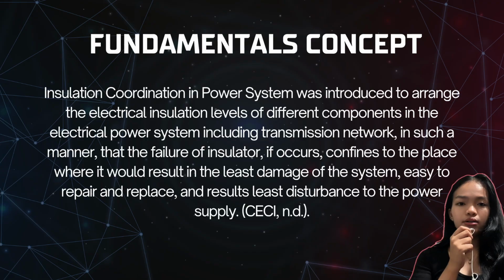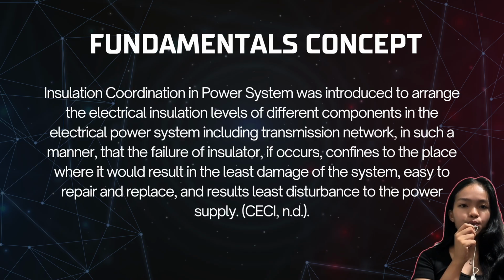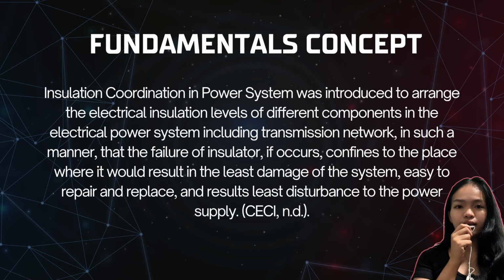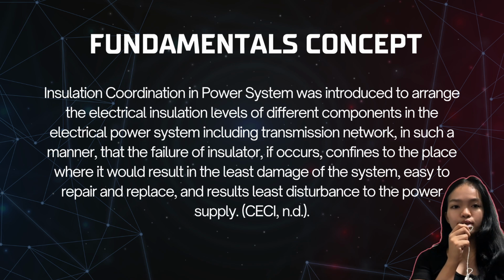According to the article published by CECI, insulation coordination in power systems was introduced to arrange the electrical insulation levels of different components in the electrical power system, including the transmission network, in such a manner that the failure of an insulator, if it occurs, is confined to the place where it would result in the least damage to the system.